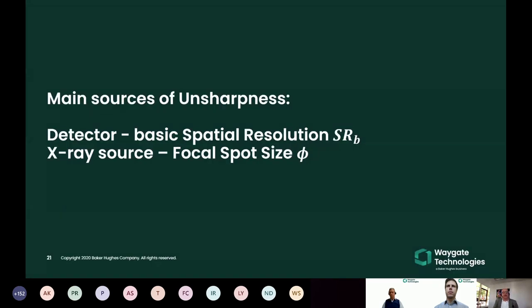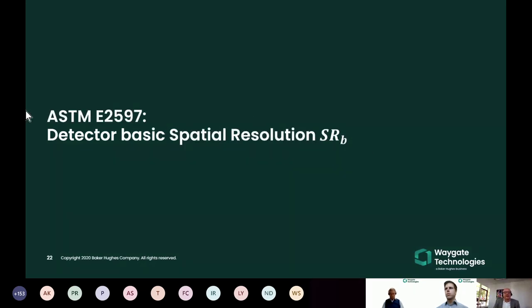The main sources of unsharpness are the detector, which has a certain pixel size or resolution, and the X-ray source, which has a focal spot size. These are the numbers specified in spec sheets. But how can we conclude from these specifications what resolution the system will actually have in a given case? Image quality is a property of the system plus the sample plus the operator, so we need to know how to process these values to find the total unsharpness.